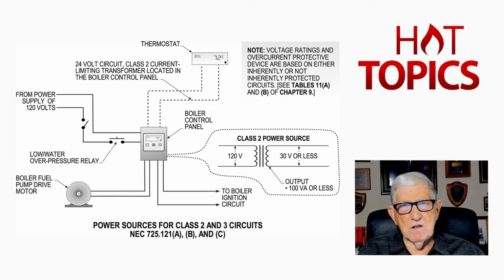And these circuits can usually be used where you need more power to keep certain types of equipment energized, like a coil on a controller and so forth. But notice the note tells you that the voltage ratings and overcurrent protection device are based on either they're inherently or non-inherently protected. And that would naturally be your Class 2 and Class 3 circuits. But your Class 1, you always have to review their outputs and their voltage ratings, so forth, in 725.41. But remember, Class 2 and 3, you go to 725.121, and to get a good feel on their outputs, go to your Tables A, B, and C of Chapter 9 in the back of the NEC codebook.